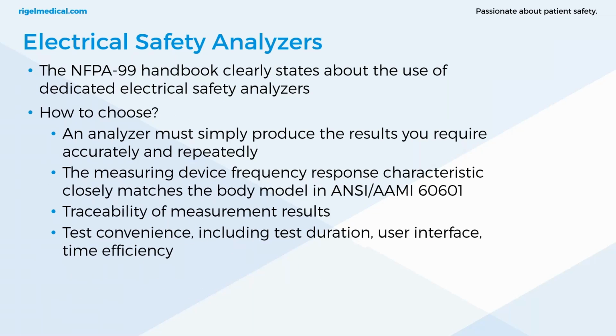The NFPA 99 handbook stipulates about the use of these. An analyzer must simply produce the results you require accurately and repeatably. So how do you pick an electrical safety analyzer? Does it produce the results you require? The measuring device frequency response characteristics closely match the body model in ANSI/AAMI. Does it have traceability of measurement results? Are the results you're getting from your device accurate? Because you need to follow that back via a traceability period through calibration to ensure that the results that you're getting are accurate and traceable as well.